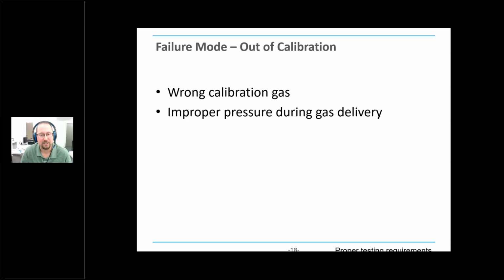They also need to deliver the gas in correctly during calibration. So this has to do with getting the gas out of the bottle down to room pressure and then letting the pump suck that gas in without increasing the pressure in the sample line. If you force it down that sample line and calibrate it, that can give you erroneous results.